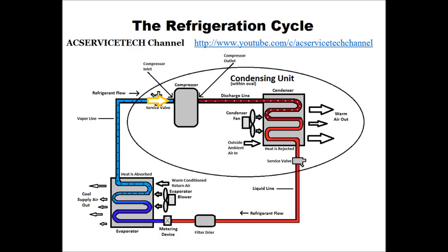All right, but if you do need to adjust a charge on a system that has a piston or capillary tube, you're going to have to set the superheat and make sure that you get it very close to the target superheat, for efficiency's sake and just to make sure that you do not have any liquid getting into the compressor on, say, cooler days and less humid days.